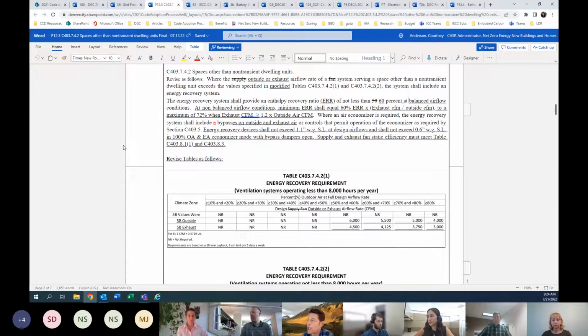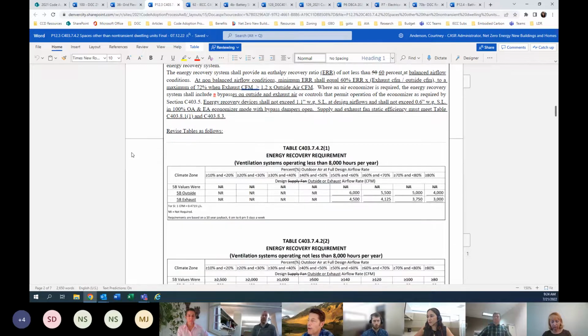And then the next change was with Chuck's input, we increased the pressure drop to 1.1 inches. The way the code's actually written, if you back the math in, they base the pressure drop around a 0.6 at sea level. And in some cases, that's a little low for current technology. And so what we did here was say, you can go with a higher pressure drop, but you would need bypass dampers in economizer mode to get down to that lower pressure.